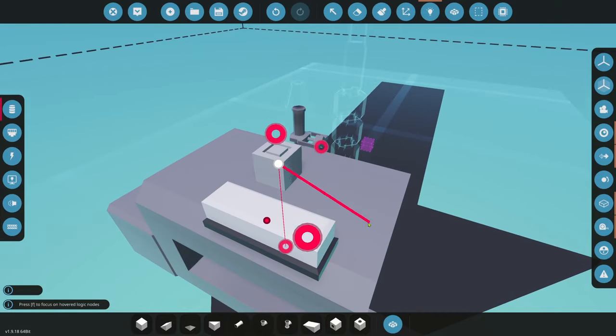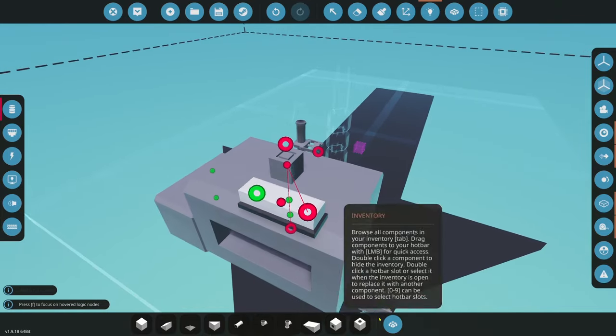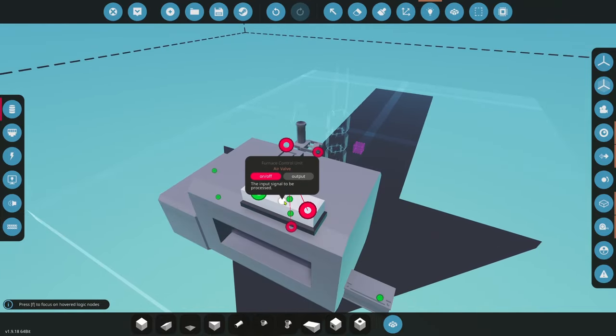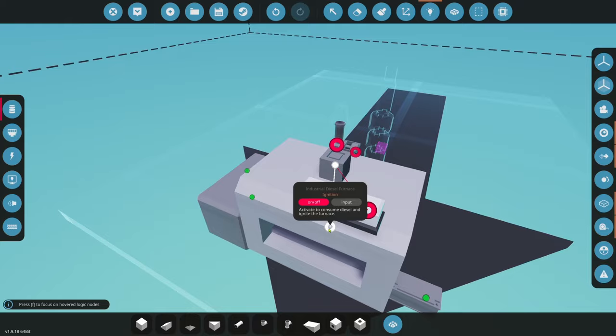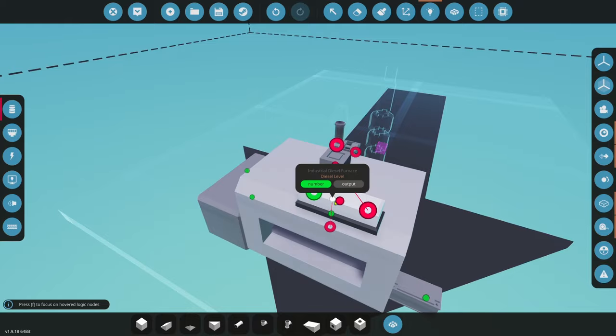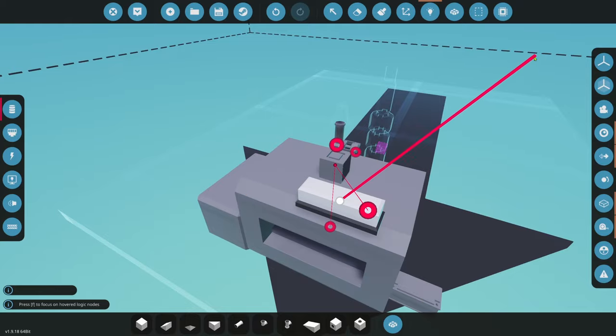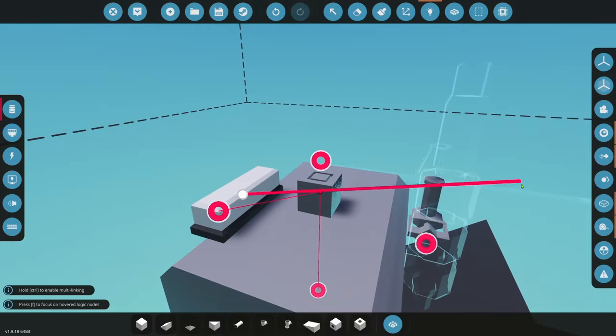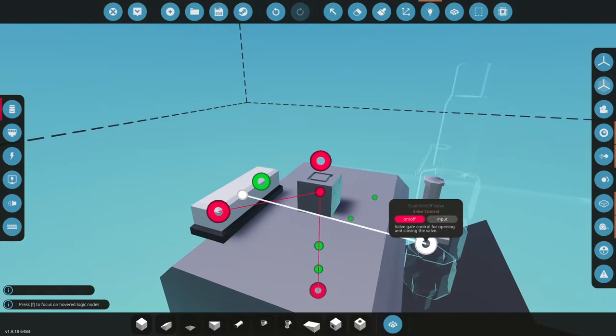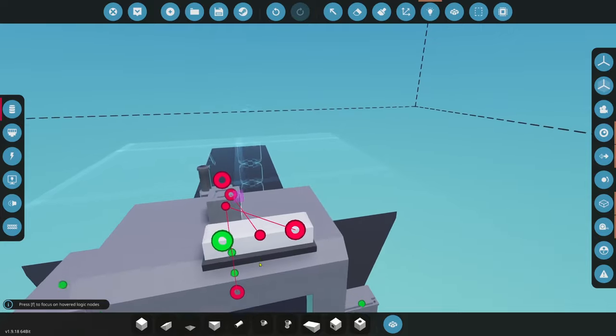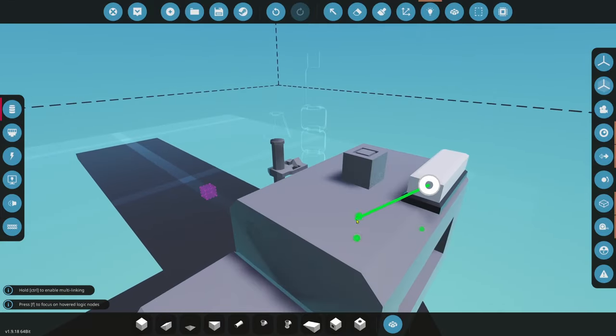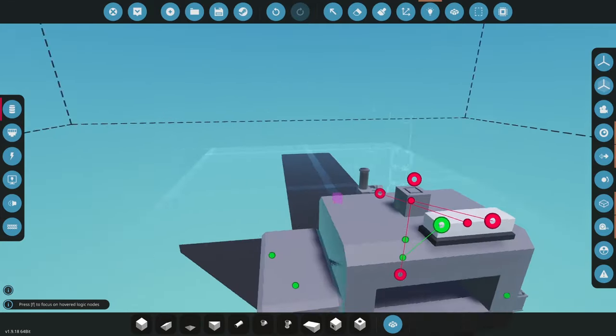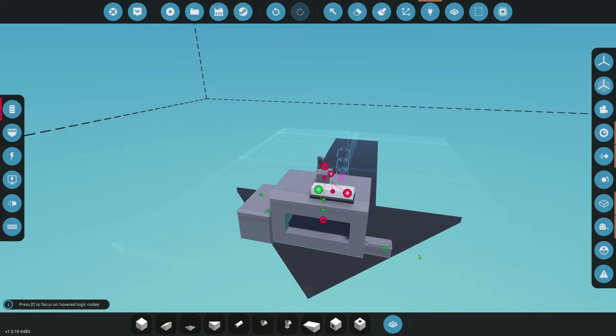We're going to grab the toggle button — the toggle button is us saying we want our steam system turned on. So we have toggle button AND the furnace temp is less than our max set, which is 120, and that's going to go to the air valve. This is an actual throttle system. What a throttle does in real life is it reduces how much air can get in to control combustion. You can only burn so much fuel with air for the air-fuel mixture. So one way to restrict the burn is by reducing the air.